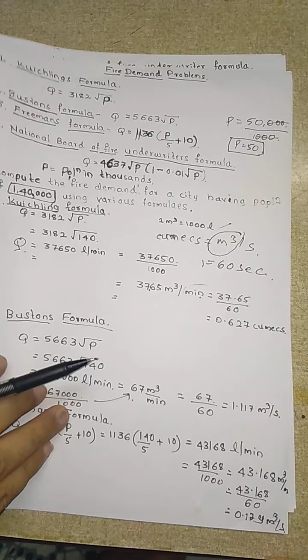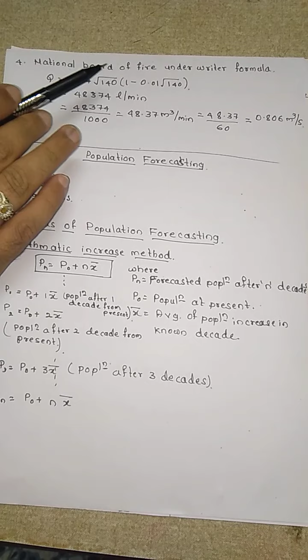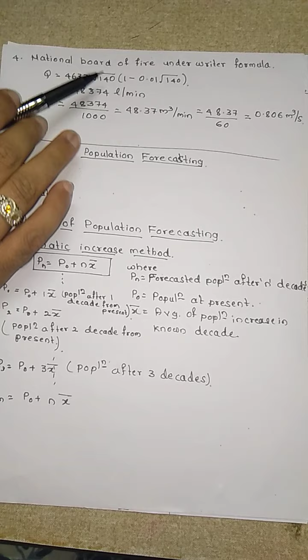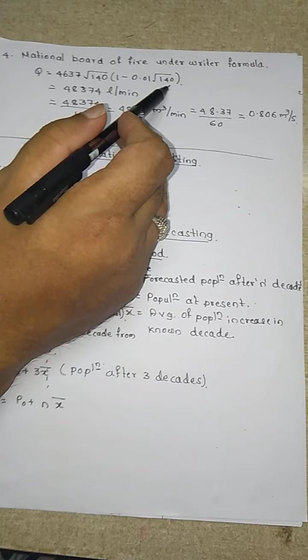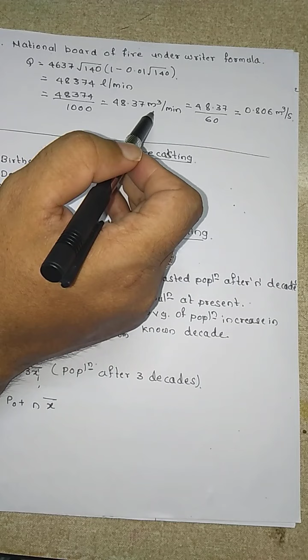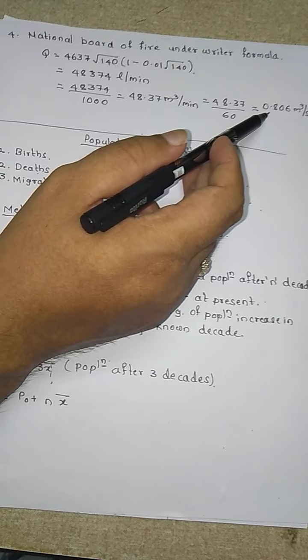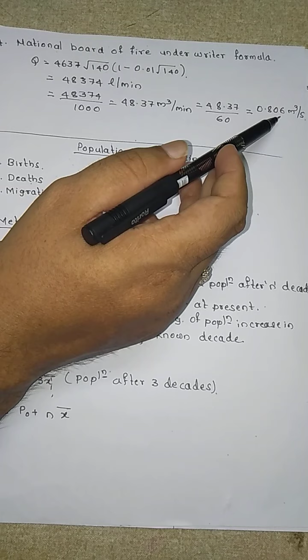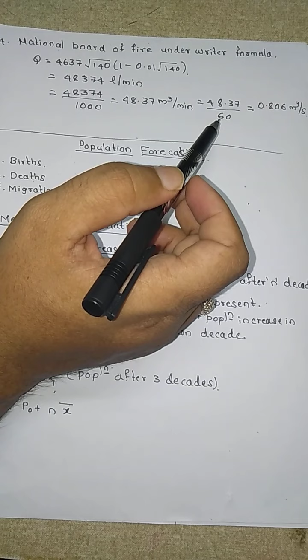Then we need to solve by National Board of Fire Underwriters formula. The formula is Q is equal to 4637 square root P into 1 minus 0.01 square root P. P is 140. Again liter to meter cube, we get 48.37 meter cube per minute. Then again minute to seconds, so we have got the answer as 0.806 meter cube per second. This is how we are going to solve the problem on fire demand.